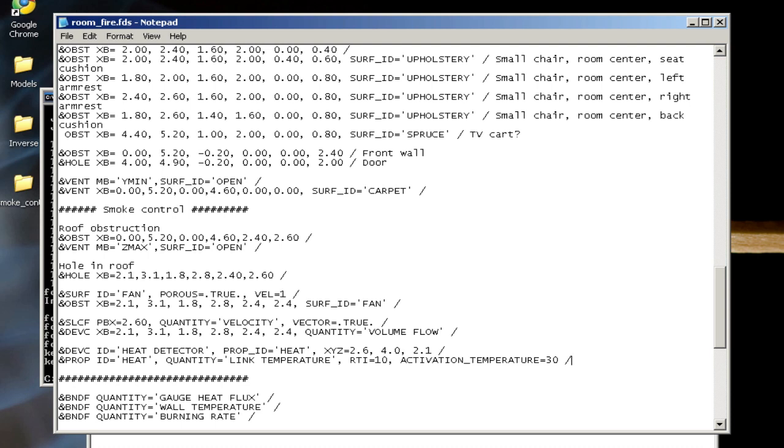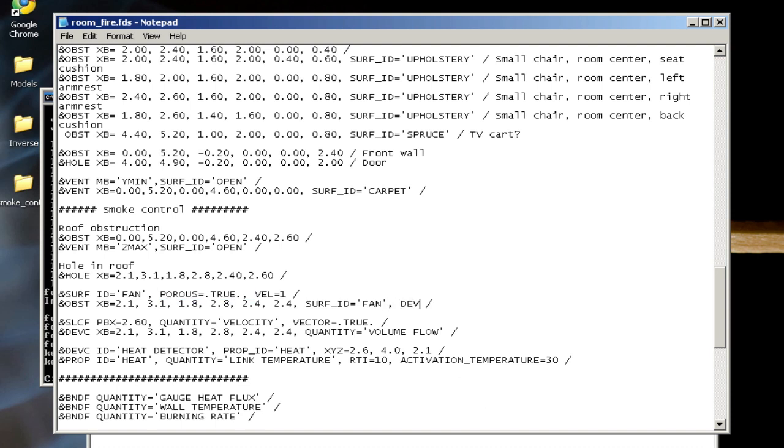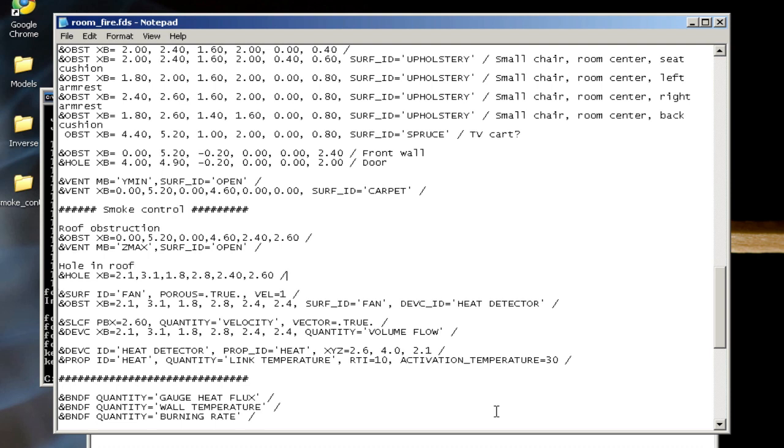I have a device and property—it's a heat detector—but I need to link the fan and the obstruction to that device. If I go up a few lines, I see that I have my obstruction here and my surface here. If I set these such that the device ID is heat detector, I'll actually wait for this device to activate before creating this obstruction. I'm going to put one more of these for the hole in the roof, so I have to place device ID heat detector on the hole and on the obstruction. That should delay the activation of the fan until these conditions for the heat detector are met, which is this activation temperature of 30 degrees Celsius.